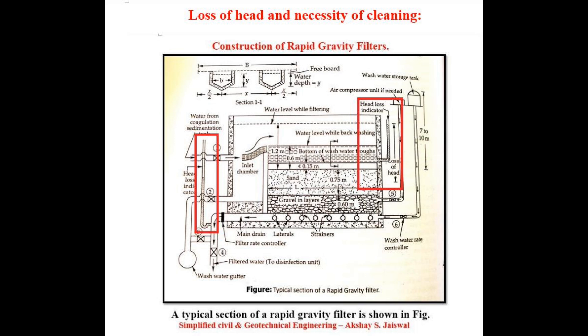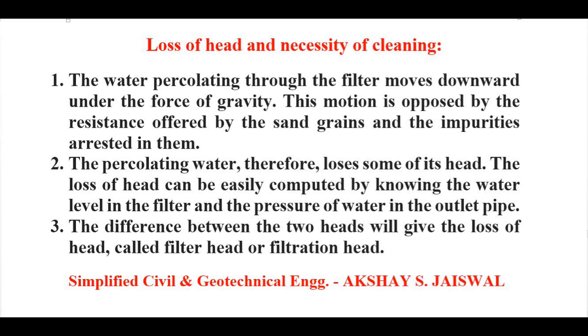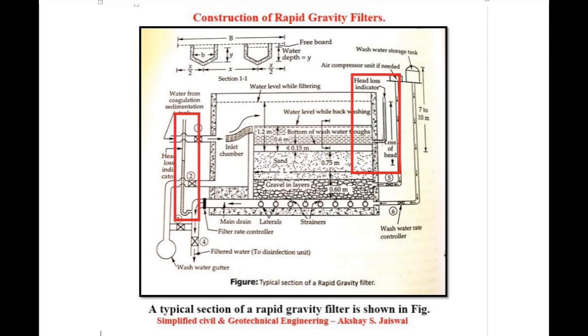Now we will see loss of head and necessity of cleaning. The water percolating through the filter moves downward under the force of gravity. This motion is opposed by the resistance offered by the sand grains and the impurities arrested in them, and the percolating water therefore loses some of its head. The loss of head can be computed by knowing the water level in the filter and the pressure of water in the outlet pipe — the difference between the two gives the filtration head. The loss of head is measured by inserting two piezometers, one in the water standing over the filter and other in the outlet pipe as shown in figure.